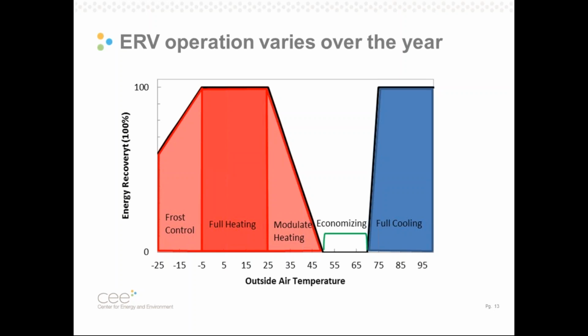Then at the bottom of the economizer zone, we start transitioning into heating weather, around 45 to 55 degrees depending on the building. At that point, our outside air temperatures are less than our inside air temperatures, and we need to heat our incoming ventilation air. This is where ERVs in Minnesota really start to shine. In these cases, we can transfer heat from the exhaust air into the supply air and actually satisfy most of the ventilation air heating load.